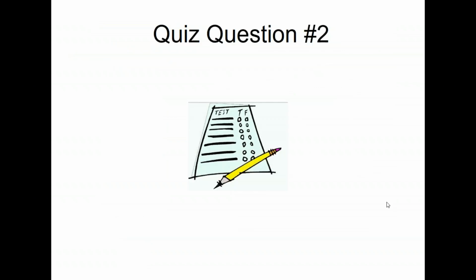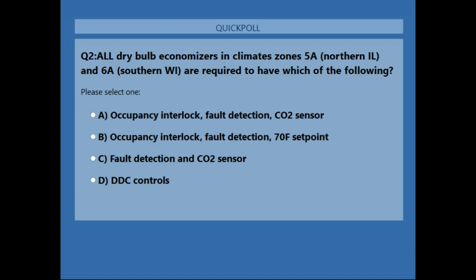All right, quiz question number 2 for you guys playing along at home. All dry bulb economizers in climate zones 5A, which is northern Illinois, Chicago area, and 6A, southern Wisconsin, are required to have which of the following? Choices are, I'm going to read them first, otherwise you guys answer the wrong things because you don't listen. A, occupancy interlock, fault detection, and CO2. B, occupancy interlock, fault detection, and a 70-degree outside air changeover set point. C, fault detection and CO2. D, DDC controls. Which of these are required for dry bulb economizers in northern Illinois and southern Wisconsin?